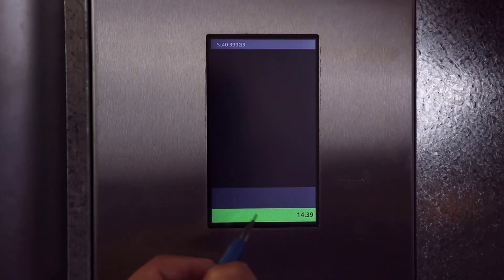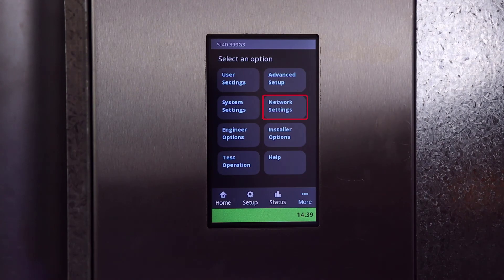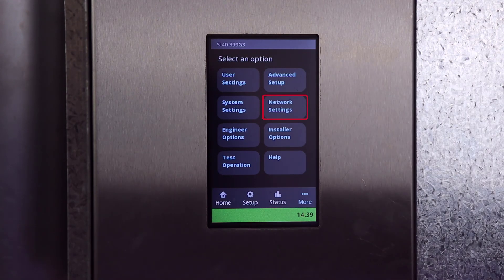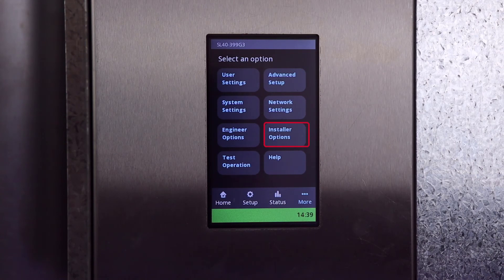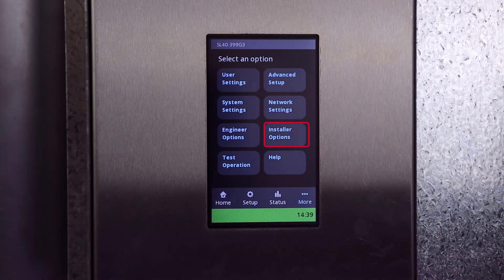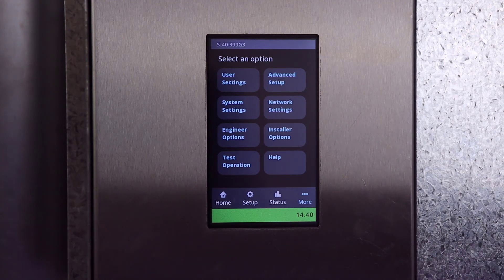Back to the More tab — Network Settings has the boiler ID for multi-boiler applications, as well as other network settings such as for a static IP address and internet portal registration. Engineer Options is for internal IBC use only. Installer Options is not for typical installations and is password protected. Here you can alter the minimum and maximum firing rate, calibrate the touchscreen, and enable password locking of load settings. If you think you need to adjust one of these settings, please contact technical support for further instruction.